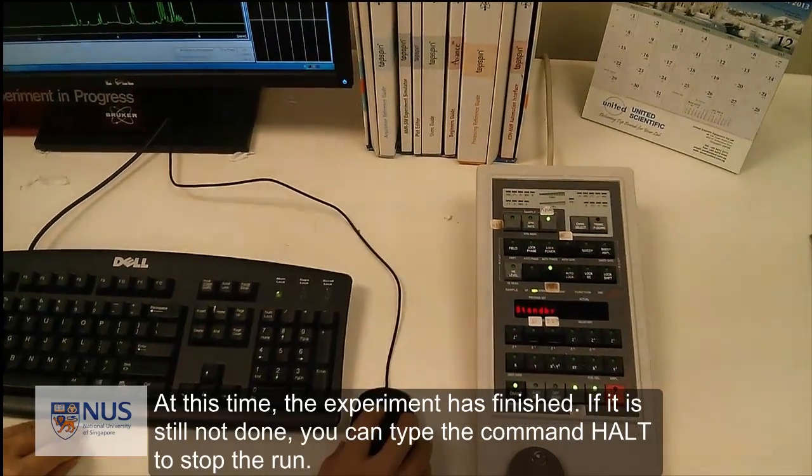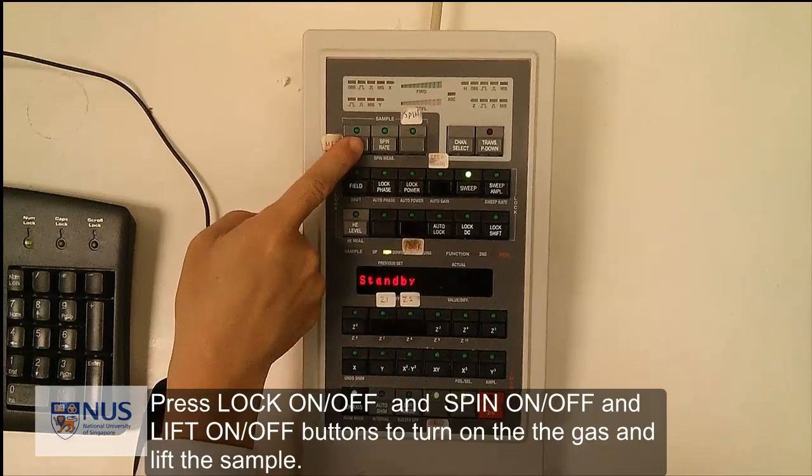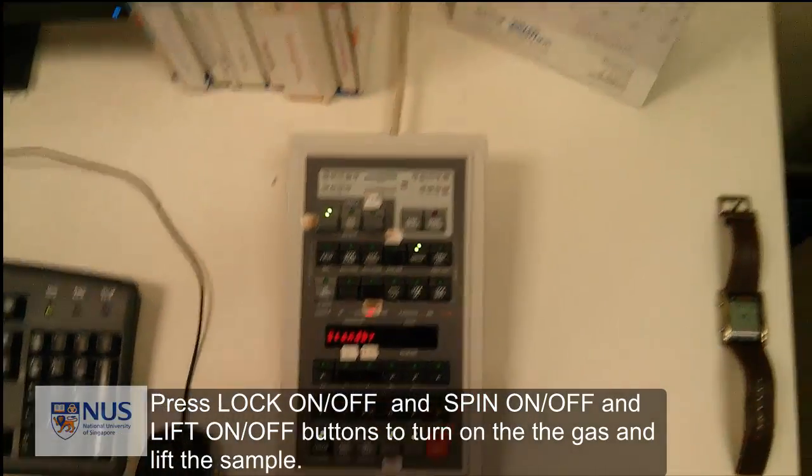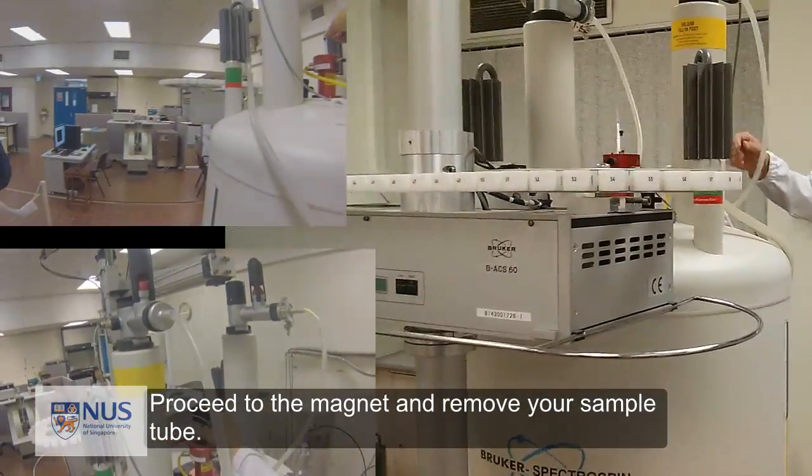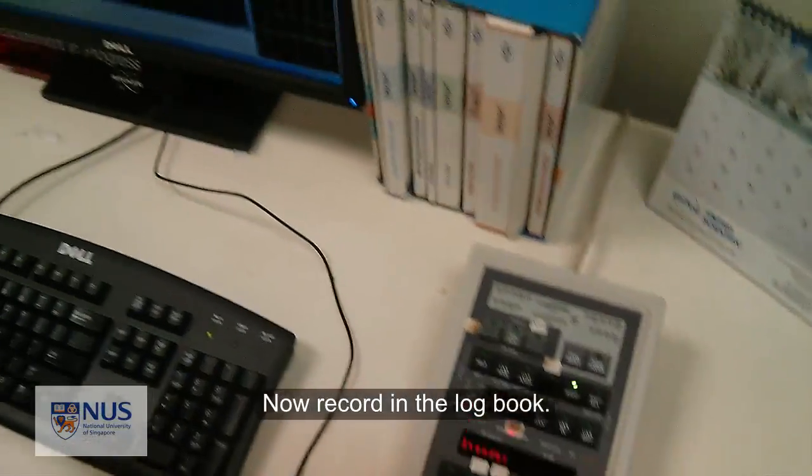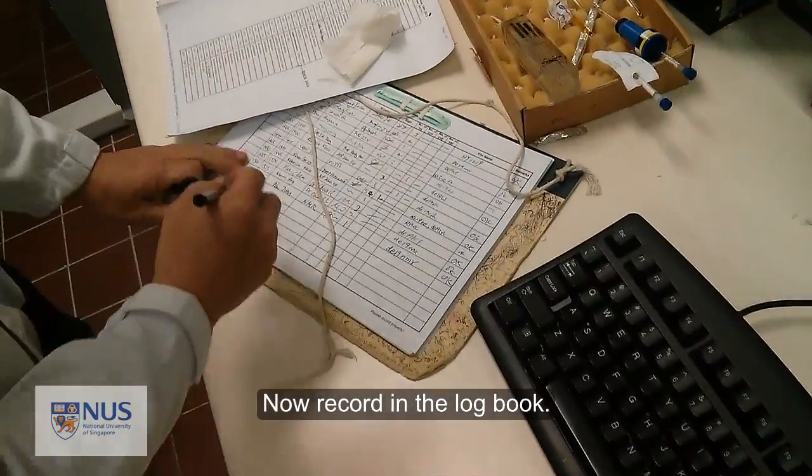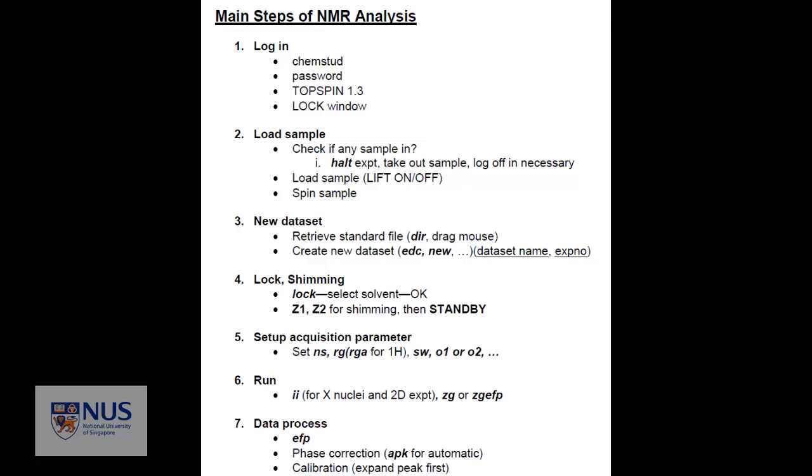At this time, the experiment has finished. If it is still not done, you can type the command HALT to stop the run. Press the lock and spin button and lift button to turn on the gas and lift the sample. Proceed to the magnet and remove your sample tube. Come back to the command center and press lift button again to turn off the air. Now, record in the logbook. These are the short summaries for the NMR technique for both sample preparation and NMR analysis. Do practice more to become better at this technique. I'm Funman. Thanks for watching this video. Have a nice day.